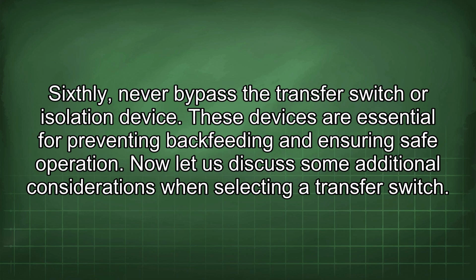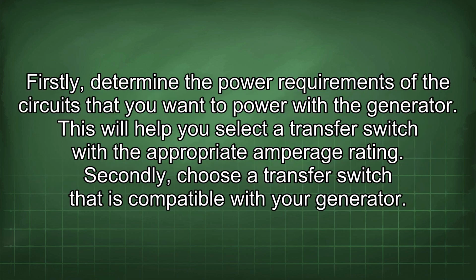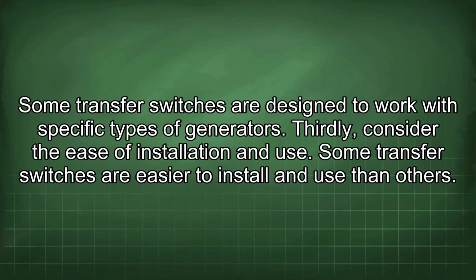Now let us discuss some additional considerations when selecting a transfer switch. Firstly, determine the power requirements of the circuits that you want to power with the generator. This will help you select a transfer switch with the appropriate amperage rating. Secondly, choose a transfer switch that is compatible with your generator. Some transfer switches are designed to work with specific types of generators.